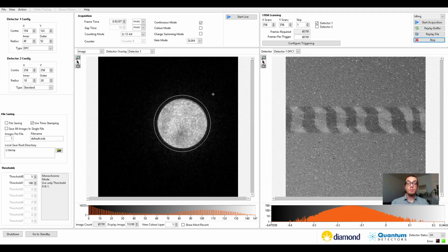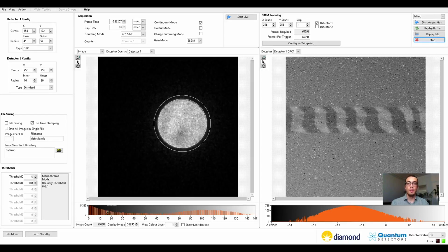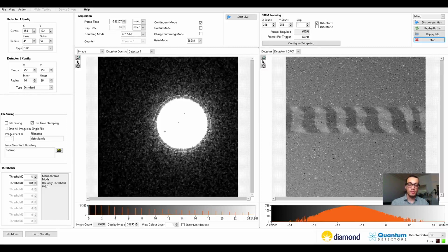As I mentioned before, we can select a particular range in the histogram to maximize the local contrast. By focusing on the small counts in the diffraction view, we can show single electron counts towards the edge of the pattern. Again, double-clicking on the histogram resets the view. The hardware counting of MerlinEM detector allows a full dynamic range within a single frame without additional noise in the lower intensity part of the frame.